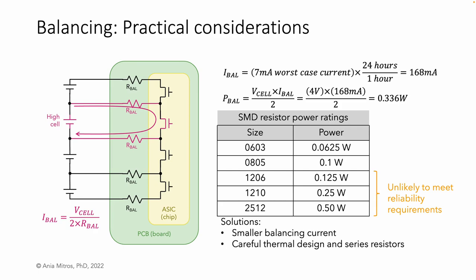In practice, then, the designer must strike a balance between the trade-offs. One solution is to use a smaller balancing current, and in the small fraction of units that show a worst-case self-discharge, balancing may need to run concurrently with battery operation. Another solution is careful thermal design and implementing each balancing resistor as several series resistors.